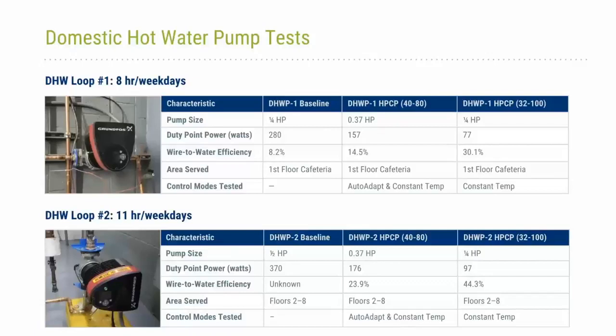So just quickly on the results for the domestic hot water pumps that we tested. The first one is domestic hot water pump number 1. This pump served the first floor and the cafeteria of the facility. And then domestic hot water recirculation pump number 2 served floors 2 through 8. Starting on the first table there, you'll see that the baseline pump was just a 1/4 horsepower pump. It's the smallest pump that's manufactured for these applications. It was originally retrofitted with the model 40-80 pump, which the sizing isn't exactly the same, but it roughly comes out to about 0.37 horsepower.